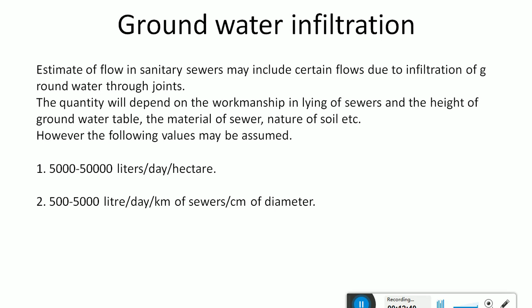diameter. Then a very important parameter here is called the self-cleansing velocity. So what is this self-cleansing velocity? Self-cleansing velocity is the one through which, even if the minimum flow is there in a sewer, the solids should not settle. That is called self-cleansing velocity, because what happens when you take the flow, we have seen the water distribution curve and also the sewage generation curve. The two peaks will occur, one in the early morning and one in the late evening. During that time the flow will be maximum and the solids will not tend to settle.